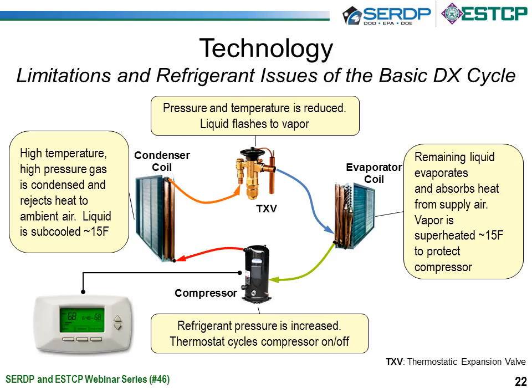The other limitation that ClimateStat addresses is at the condenser coil, when the high pressure gas is condensed and then subcooled, but it can only get within about 5 or 10 degrees of ambient. So if it's 95 outside, you can't really cool that refrigerant to much below, say, 100 or 105 in the best case. And then when you're trying to achieve 45 degrees, you've got a long way to go.